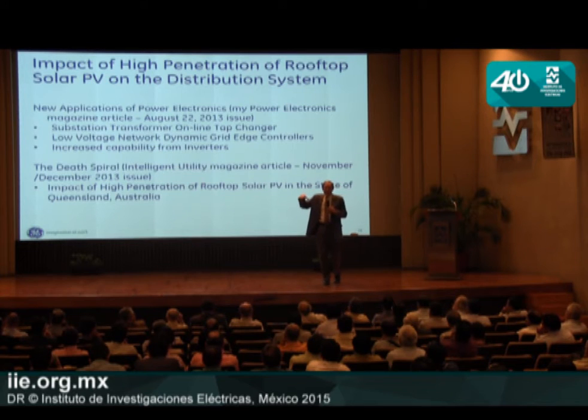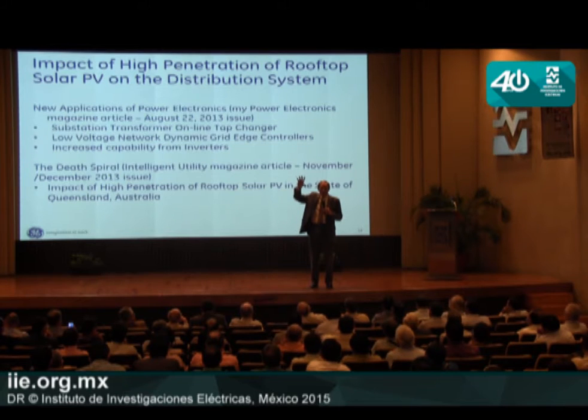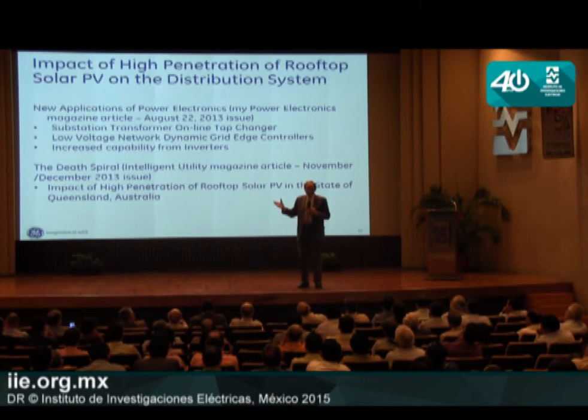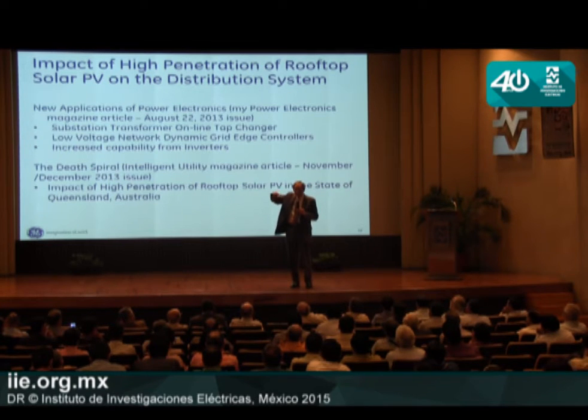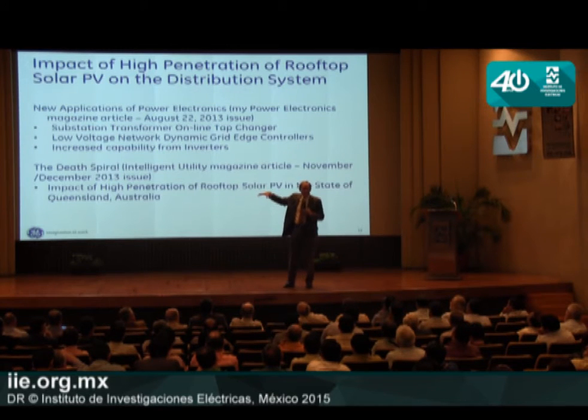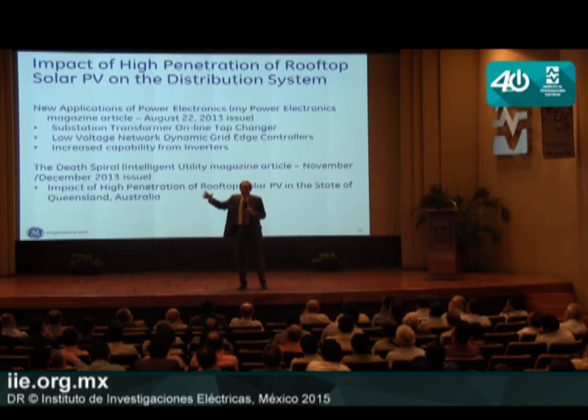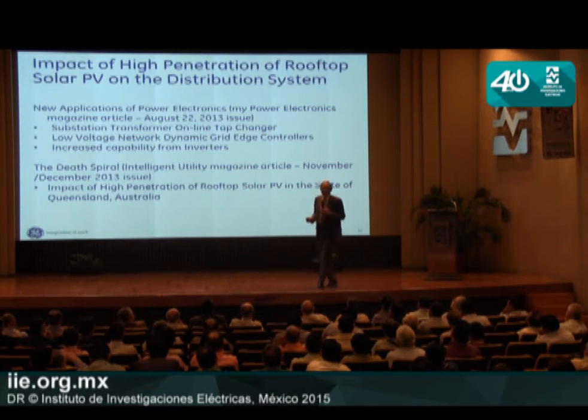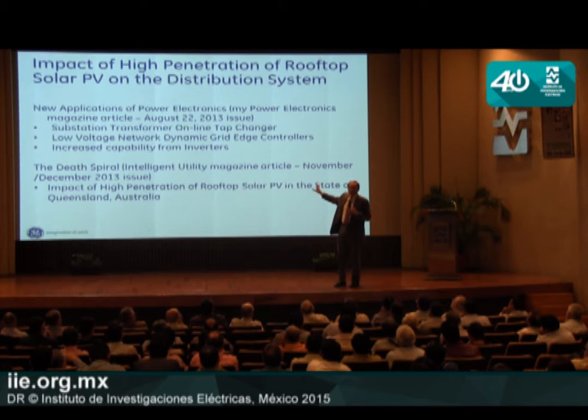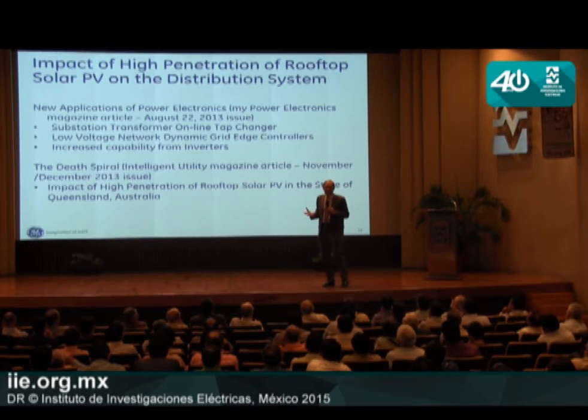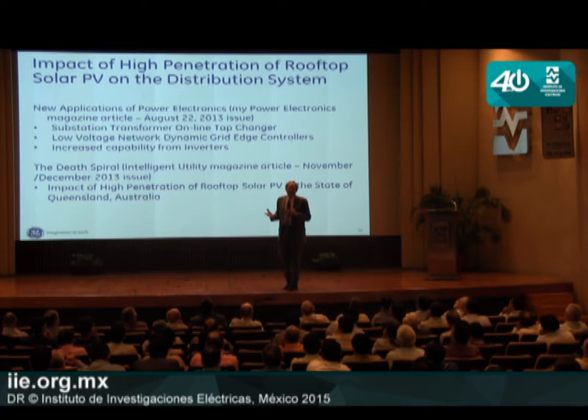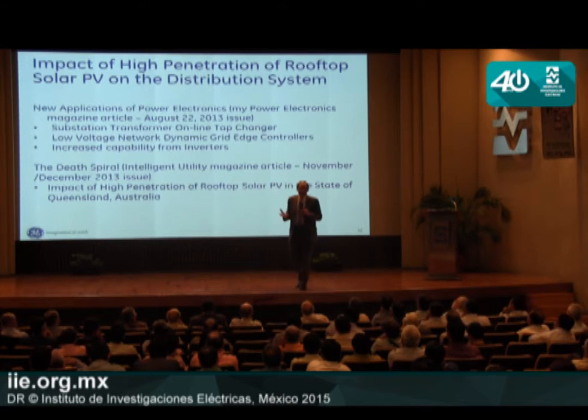In the substation that feeds that feeder, there's an online tap changer. A tap changer is mechanical, with 32 discrete positions, and its objective is that as the primary voltage changes, the tap changer changes tap positions to keep the secondary voltage constant, because at the customer's premise you want the voltage to be constant. Normally on this feeder with no PV, the tap changer operated 5 times per day, with a designed lifetime of 30 to 40 years.